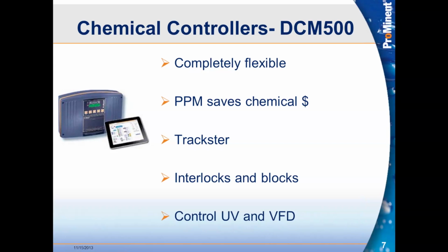The other side of this too, and I'll talk about this a little bit more when we get to the UV section of the presentation, is that we have the ability to control UV off of this. Because we can do free chlorine and total chlorine to such a great resolution, we can take that derived combined chlorine reading, and then we can tell a UV system to turn up, to turn down, to turn off, to turn on, and in turn this is going to have a lot of savings for the facility.